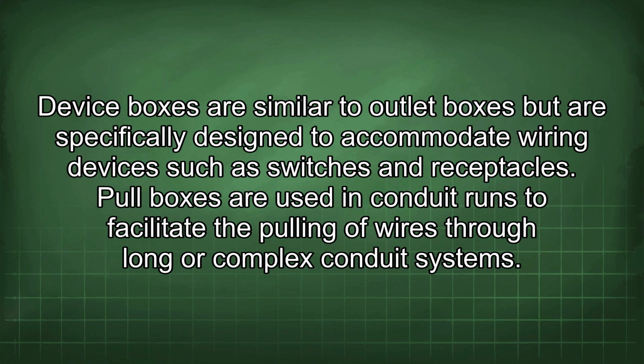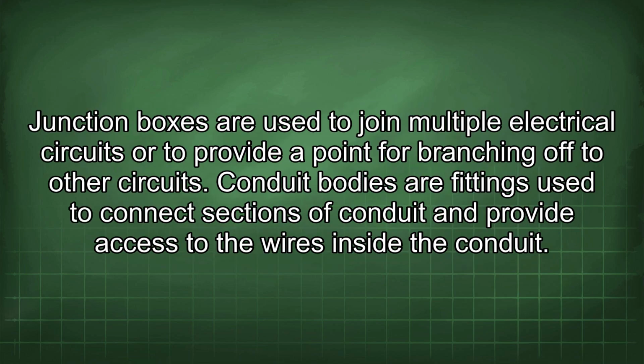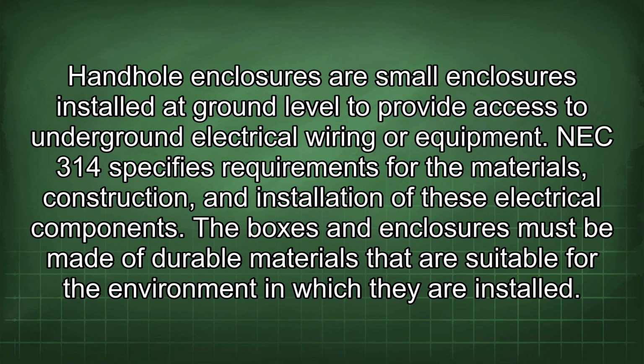Pull boxes are used in conduit runs to facilitate the pulling of wires through long or complex conduit systems. Junction boxes are used to join multiple electrical circuits or to provide a point for branching off to other circuits. Conduit bodies are fittings used to connect sections of conduit and provide access to the wires inside the conduit. Handhole enclosures are small enclosures installed at ground level to provide access to underground electrical wiring or equipment. NEC 314 specifies requirements for the materials, construction, and installation of these electrical components.